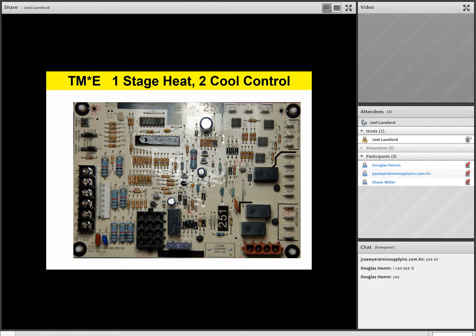And so remember, team, the ECM motors always have power to them. Anytime you power the product up, or the furnace up, or the air handler up, anytime you power up an ECM product, it's going to have power to the motor all the time. And then what's going to happen, we're going to provide it with 24-volt commands to tell it what to do. Now those 24-volt commands could be a jumper setting, for instance, on a variable speed control board, or they could be hard physical motor settings that we're going to see, for instance, on this board. We have a low cool and a high cool in the upper right-hand corner of your picture there. And so those are actual motor speed taps.